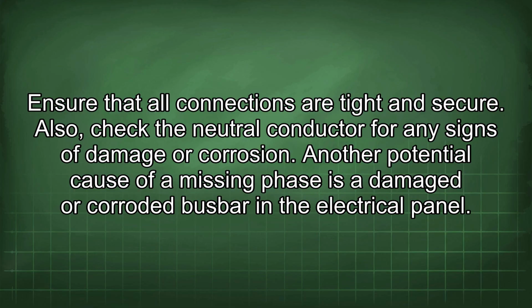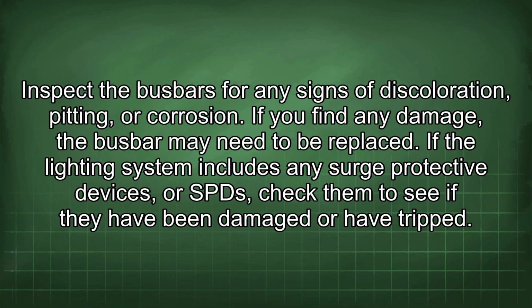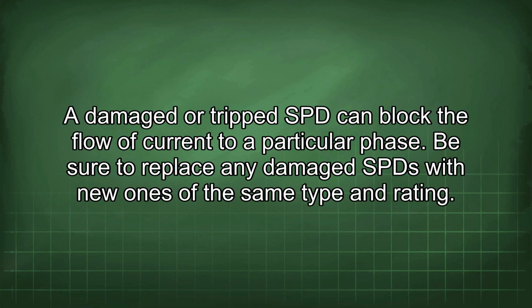Another potential cause of a missing phase is a damaged or corroded busbar in the electrical panel. Inspect the busbars for any signs of discoloration, pitting, or corrosion. If you find any damage, the busbar may need to be replaced. If the lighting system includes any surge protective devices, or SPDs, check them to see if they have been damaged or have tripped. A damaged or tripped SPD can block the flow of current to a particular phase. Be sure to replace any damaged SPD with new ones of the same type and rating.